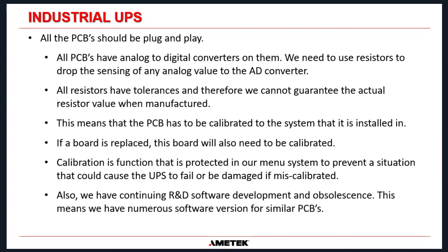So yes, in an ideal world, it would be fantastic if the PCBs would be plug and play. But unfortunately, we just can't do that. It's not possible. So in near enough every situation, you're going to need a field service guy to come out and recalibrate the board when it's put inside a system. Okay, hopefully that explained that one.